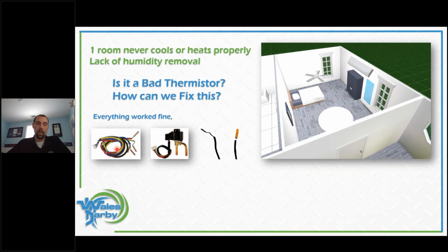So if they're off and they're telling me bad readings, sensing temperatures coming back that are wrong, they're going to maybe shut down this expansion valve and stop putting refrigerant into the indoor unit. If maybe my pipe thermistor is giving me a bad reading. I had one recently. Guys replaced multiple parts, even the whole outdoor unit, and still couldn't get the outdoor unit to come on. Pipe thermistor, cheap little part. Pipe thermistor was telling the outdoor unit it was 138 degrees inside. It wasn't. It was about 30 degrees inside. So that thermistor was telling the coil, basically the outdoor unit, that my coil's hot. I don't need any more refrigerant. Don't turn on.